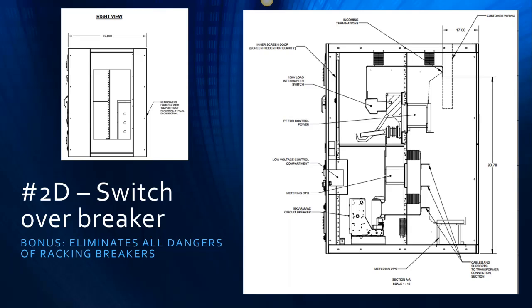Having the isolation switch avoids that, but most importantly, it avoids the necessity for racking for simple lockout tagout. So you open the switch up to isolate, you lock it out, and you no longer have the necessity to rack out the breaker, a mechanically complex operation, in order to achieve lockout tagout requirements. And opening that switch and locking out takes merely a few seconds. And again, it's an arc rated switch, so it requires no PPE for that operation.